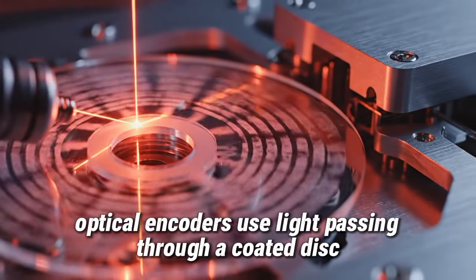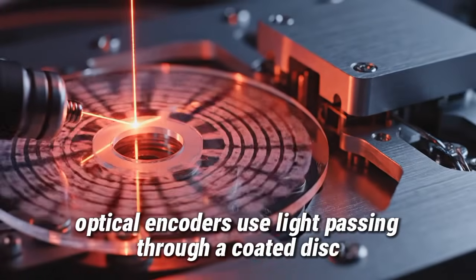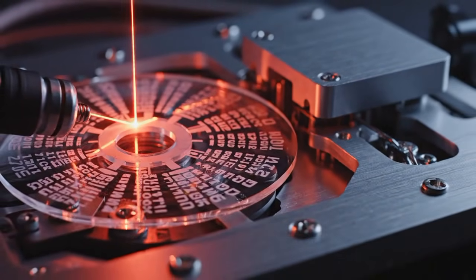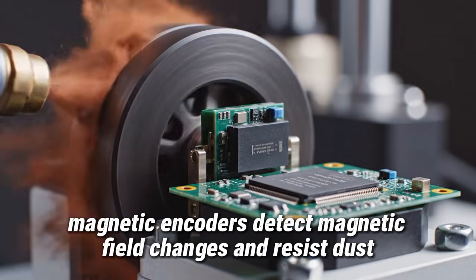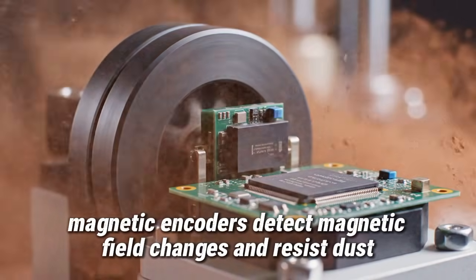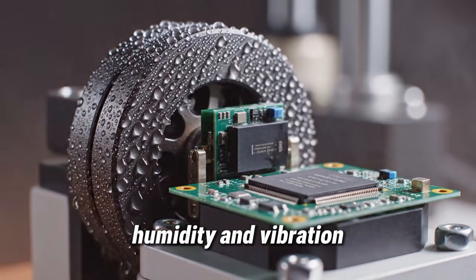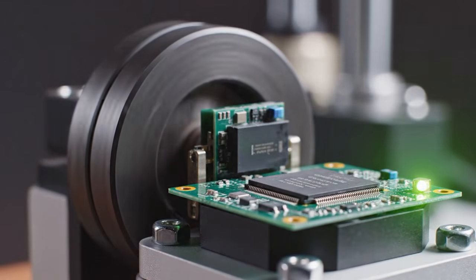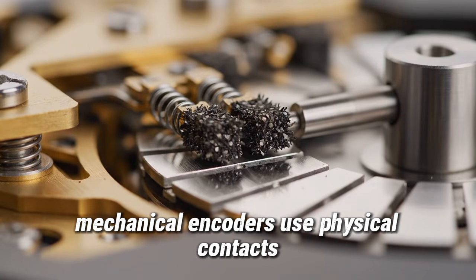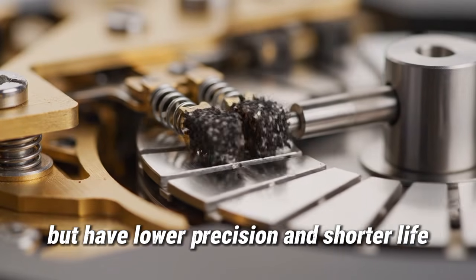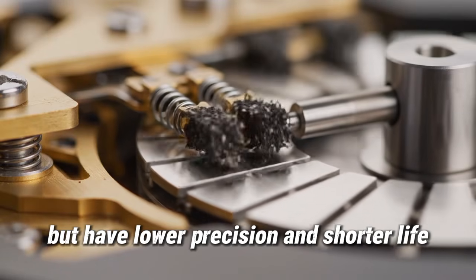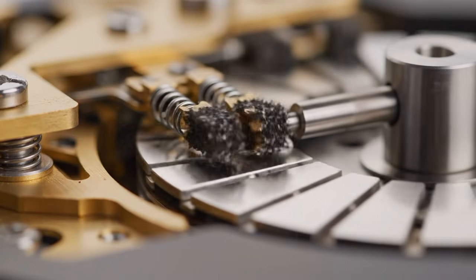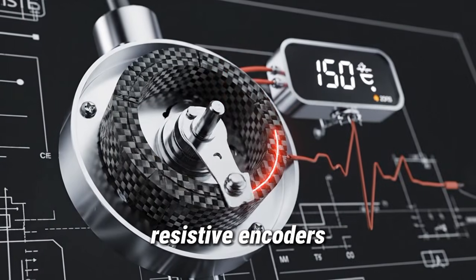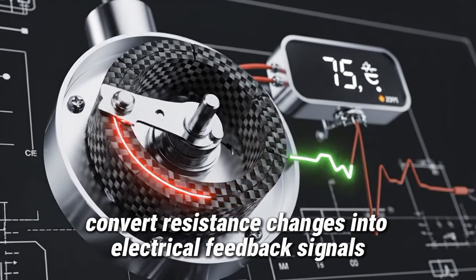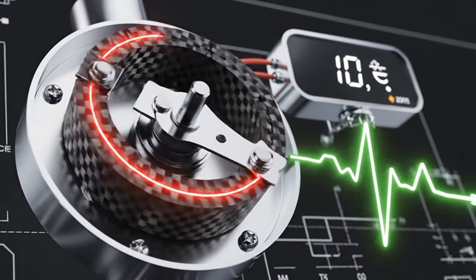Optical encoders use light passing through a coated disc for very high resolution. Magnetic encoders detect magnetic field changes and resist dust, humidity, and vibration. Mechanical encoders use physical contacts but have lower precision and shorter life. Resistive encoders convert resistance changes into electrical feedback signals.